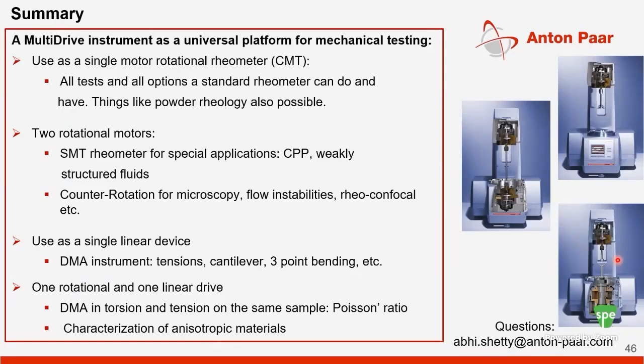Can you comment on extensional rheology measurements possible with the device for liquids? I didn't have time to talk about that today, but we do have capability where you can use a setup with two parallel plates, put a liquid sample there, and do step strain type experiments to understand capillary breakup or filament breakup. You can couple this setup with a camera, take images, analyze how the filament diameter thins, fit an exponential profile to that thinning, and get something like a relaxation time. So filament breakup type experiments are also possible with this device.